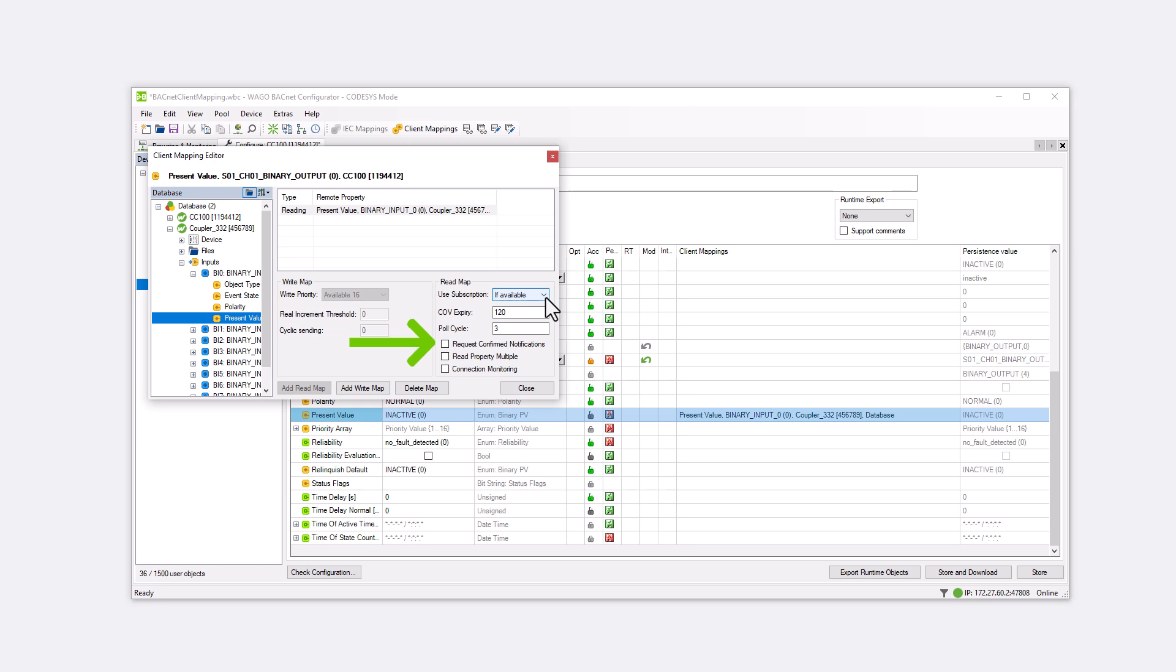Request Confirm Notification: Here, you can select whether a COV notification from the server is confirmed by the client. If this option is selected, the server expects a confirmation from the client after sending the COV notification. If this feedback does not arrive, the server resends the COV notification. Generally, this function remains disabled, as it can significantly increase bus load and should only be used consciously.